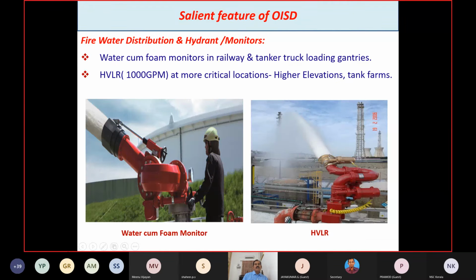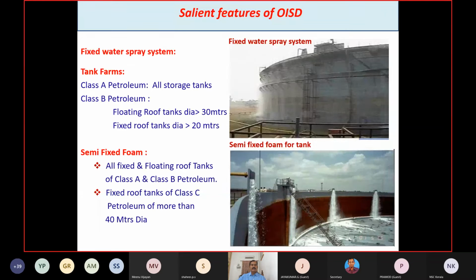And for fire water distribution and hydrant monitors, water foam monitors in railway and tank truck loading gantries are to be provided, and HVLR, that is high volume long range monitors, at more critical locations of higher elevations and tank farms should be provided. It is available for water foam monitors and also for high volume long range monitors.